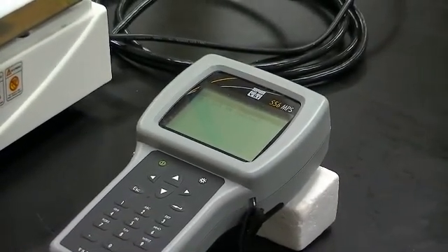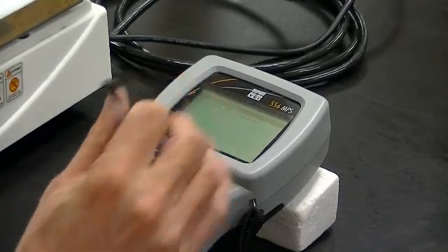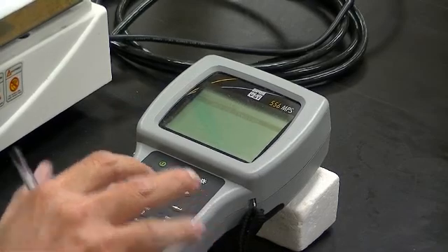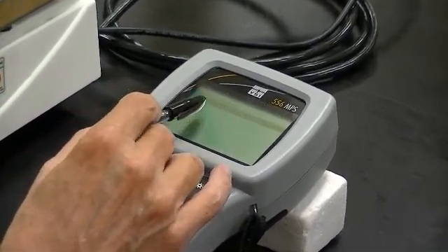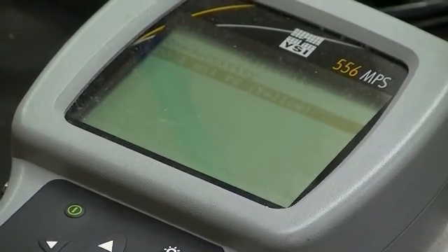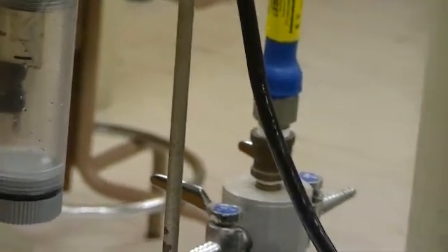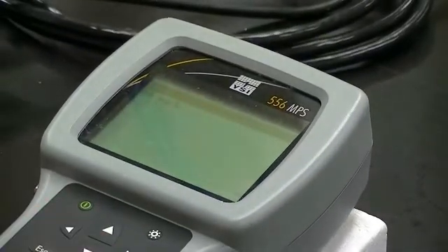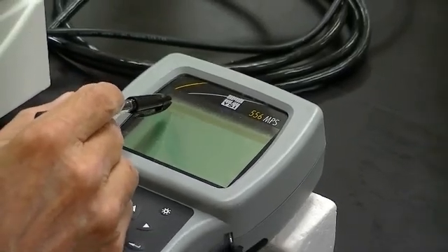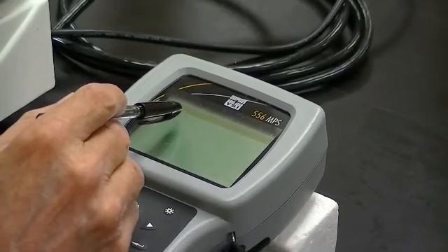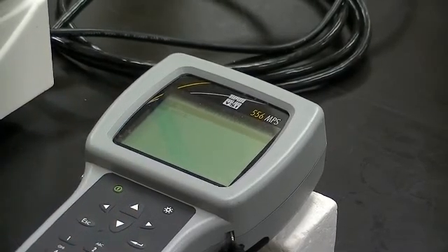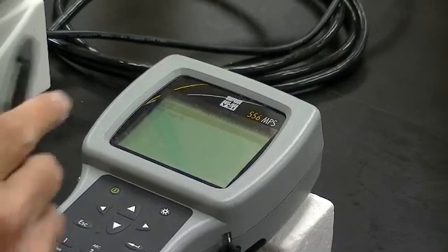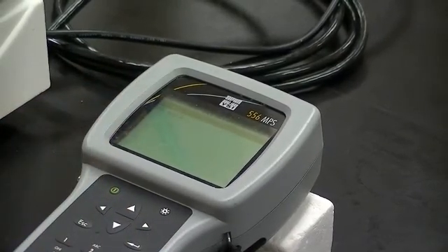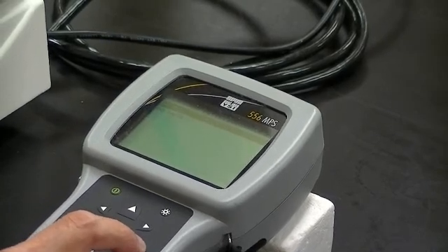And now you have the two choices, just like you saw with the salinity, conductivity and DO. Only now you want to arrow down and highlight DO milligrams per liter, yellow. And the yellow means that the sensor here is the yellow cartridge. There's also a blue one that has a different calibration. All right, so once you get that, you hit the return key. And now you have two items that say DO percent and DO milligrams per liter. Now we're air calibrating in water saturated air, so we select DO percent, which is the top one. It should already be highlighted, so you push return.